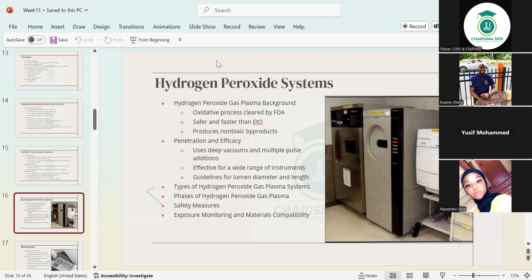Okay? So the penetration and efficacy use deep vacuums and multiple pulse additions, effective for a wide range of instruments. There are guidelines for lumens, which are the instruments with cannulas, with channels in them. The diameter and length have standards. There are certain diameters that you can put in there. A lot of times you'll be going with the IFUs, but it has penetration efficacy such that it's able to handle a wide range of instruments.